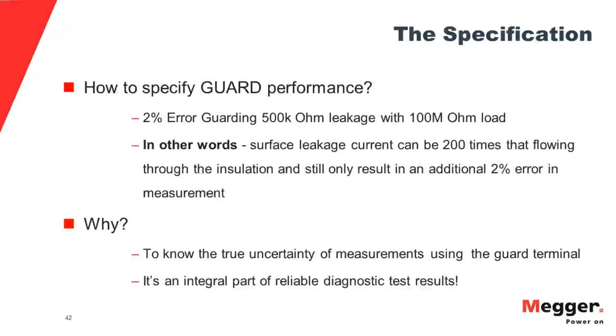Okay. And guard terminal performance, this is something you want to look at when you're purchasing a tester. It's the way that tester manufacturers who try to go to market primarily on price will emphasize the positive aspects of their product, but de-emphasize or not mention the negative aspects. And one of the areas in which they can save on design costs and manufacturing costs is on a guard terminal. So it takes a good degree of engineering to properly design a guard terminal, because this is a relatively low resistance circuit that is competing with a high resistance circuit, which is your measurement circuit. And it's competing for a limited amount of leakage current.